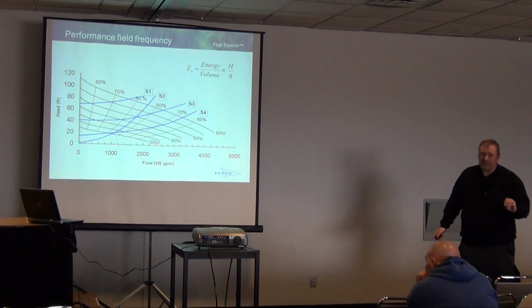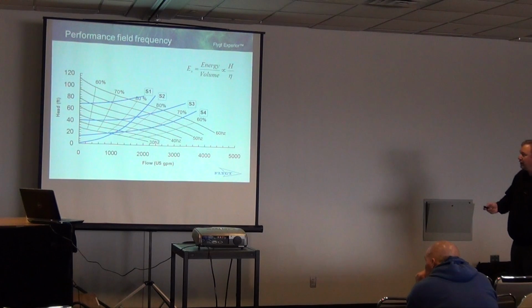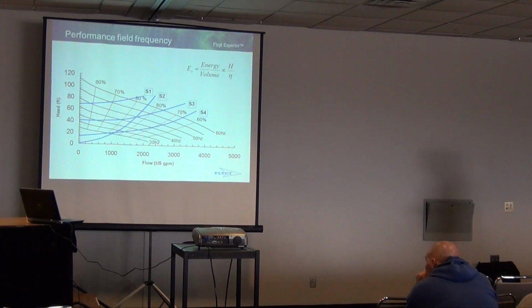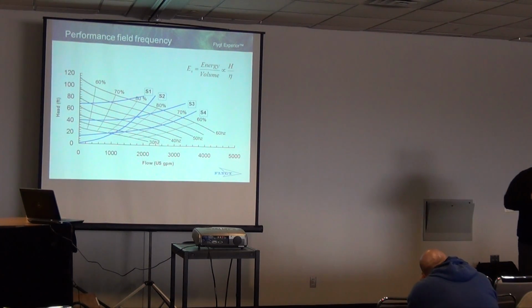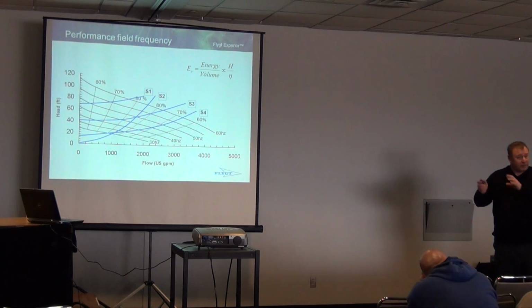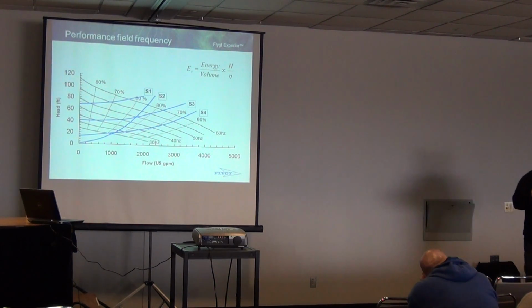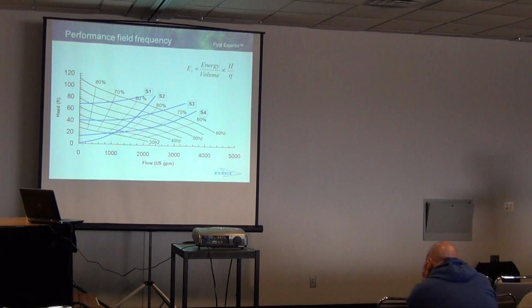So when we look at applying these and we look at simple pump curves, a lot of VFD manufacturers over the years, you get the benefits of the soft starts and stops with the VFD, no doubt. With these units, we can do phase conversion. So we can go from single phase to three phase. If you've got single phase power areas in your communities and you want to put three phase pumps in with more torque, these can absolutely do that. That's been a big part of using VFDs in the wastewater world over the last few years. But one of the things that I want to talk about is VFDs and these units can be grossly misapplied as well.